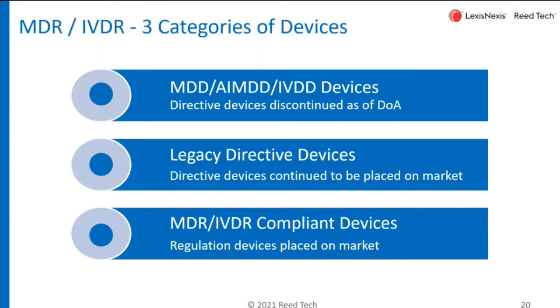It's significant in that there is actually a touch point for these devices with EUDAMED's device module in the event of a serious incident. With these particular devices you will need to report that serious incident, and as a prerequisite of doing so you'll need to register those devices in EUDAMED. There are some special conditions about how you go about doing that, but that would be the only touch point.